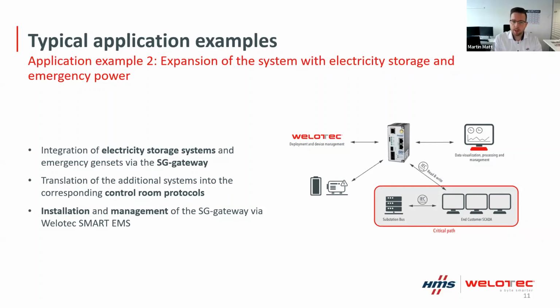We at HMS dig deeper into battery energy storage systems. We have good and extensive CAN knowledge, which is mostly used in these battery storage systems, but we can also connect ourselves to gensets through Profinet, Profibus, or EtherNet/IP. Depending on the size, they communicate using Modbus or one of the industrial protocols. So these additional power sources or power storages can be installed in these situations, but natively they cannot communicate to the SCADA system. So you need something in between, which for the battery or the genset simulates a management system, and something that simulates an electrical device towards the SCADA system.